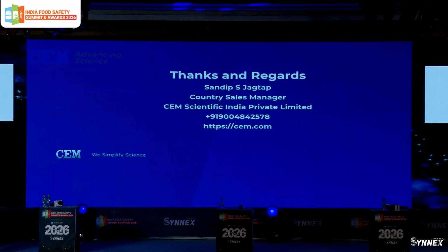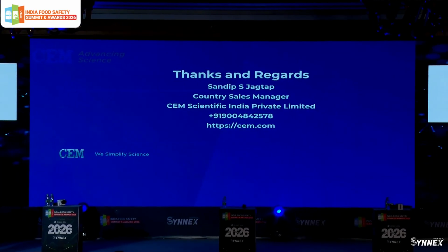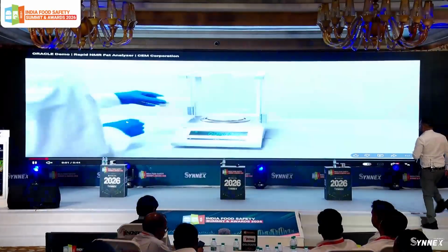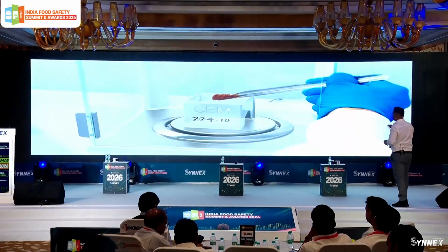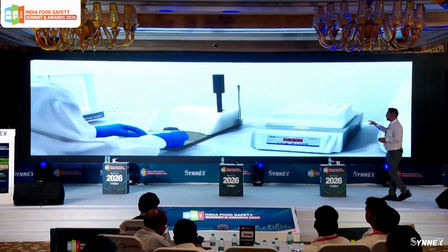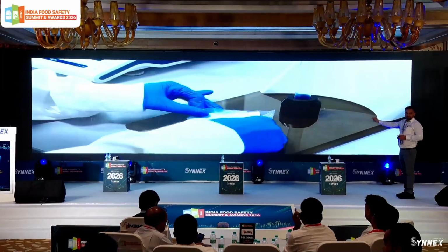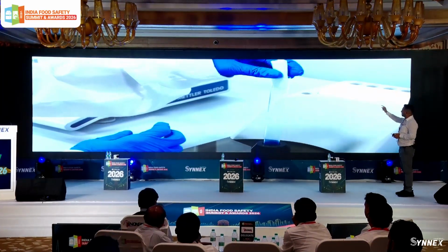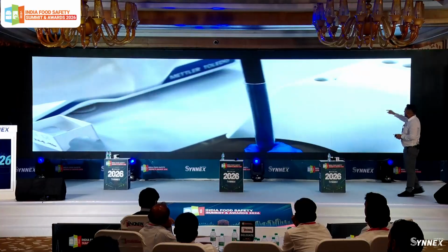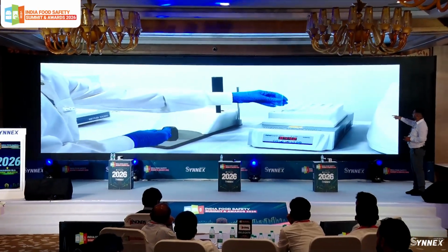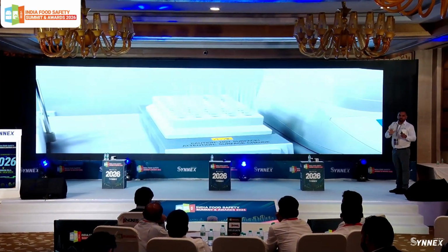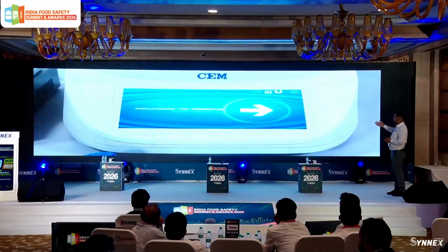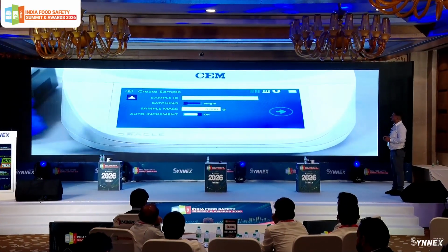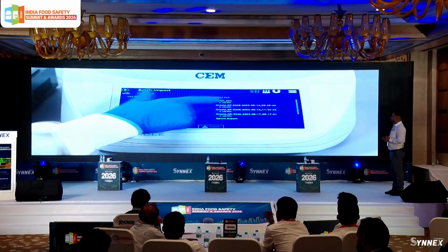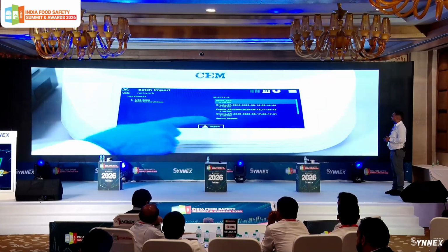Can I have the video? So quickly, I will show you a one minute video. You can see the sample is kept. It's weighed. It's just flipped in the butter paper. It is kept in the NMR tube, and the same tube is kept in the system. Here, if you are not using any moisture drying, you can use the hot block. You keep it here, it will give you the fat content. You can transfer the data to LIMS also.